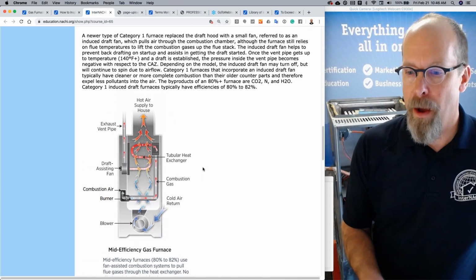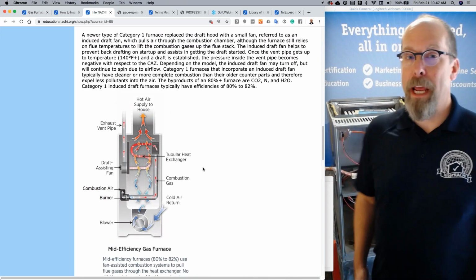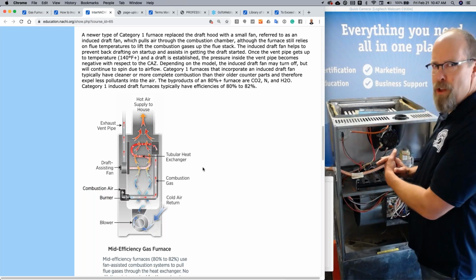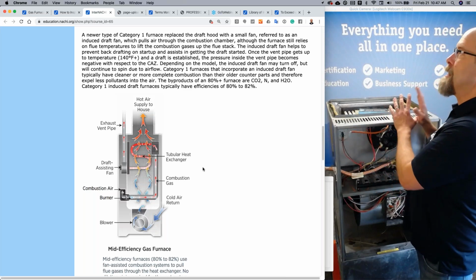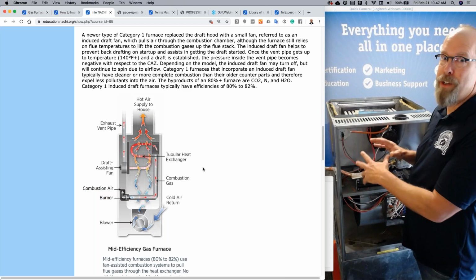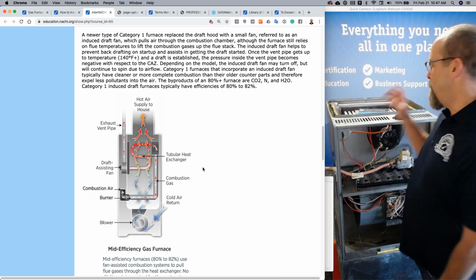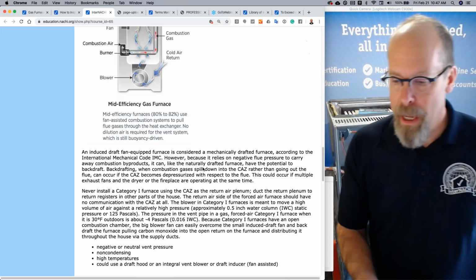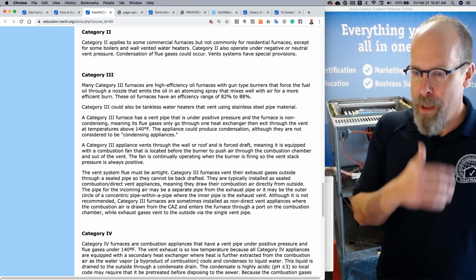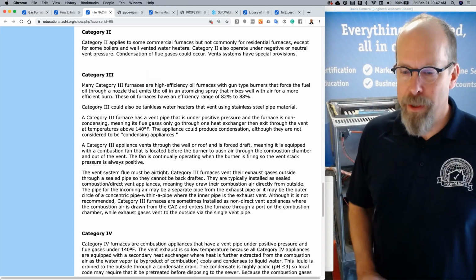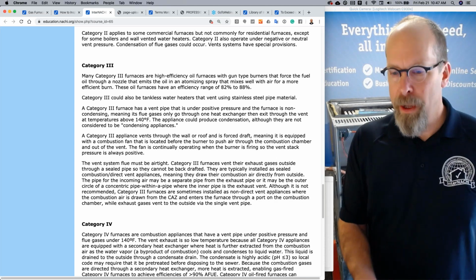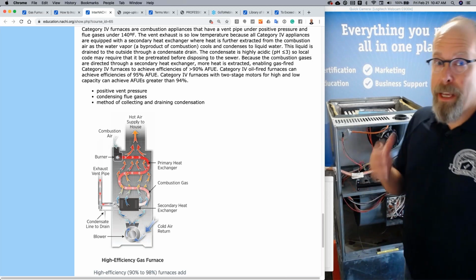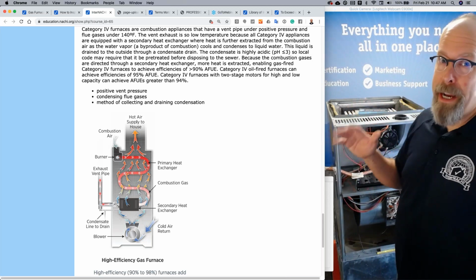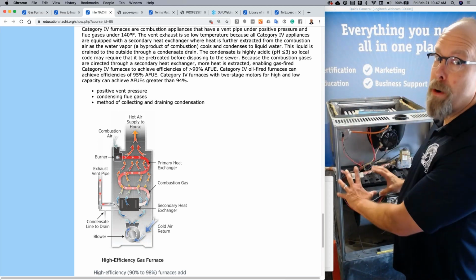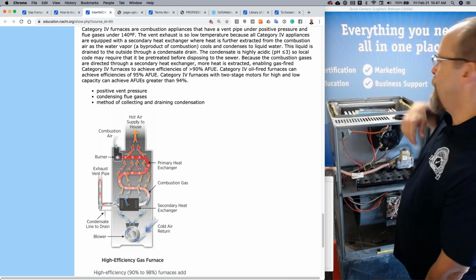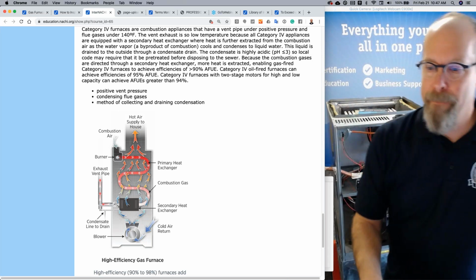Category 1 right here, mid efficiency. Now we're getting better with burning the fuels. Did I say low efficiency? We're getting better with burning the fuel. It wastes a little bit less fuel. It's a little bit more efficient. So mid efficiency, right? Category 1, metal vent pipe. You can touch the burners. Category 2, not common for homes, commercial furnaces really. Category 3 is really oil burners. Category 4 is the common heating system, high efficient, high 90s, plastic vent pipe, enclosed burner chamber, fresh air intake, exhaust vent pipe, secondary heat exchanger inside, high efficiency. Yep.